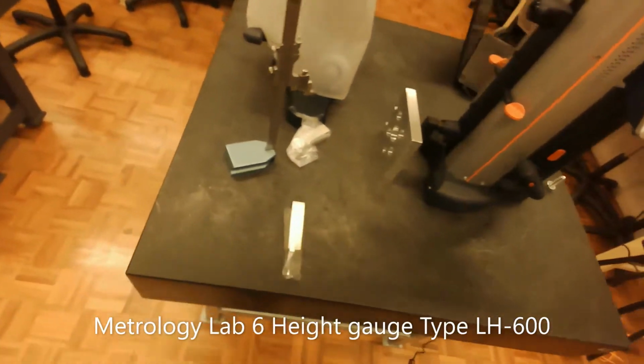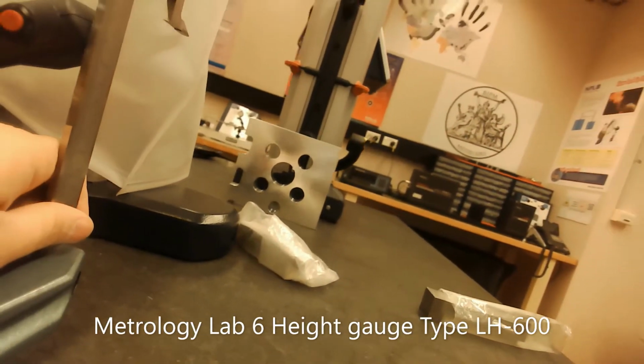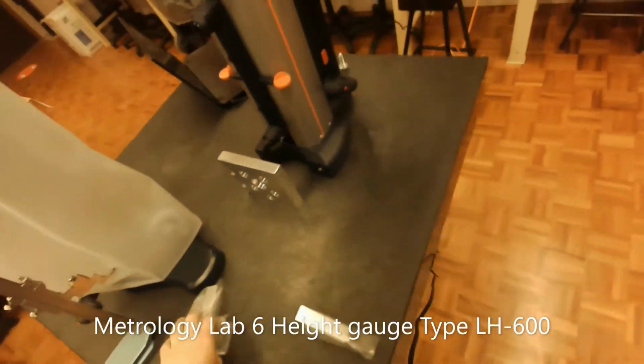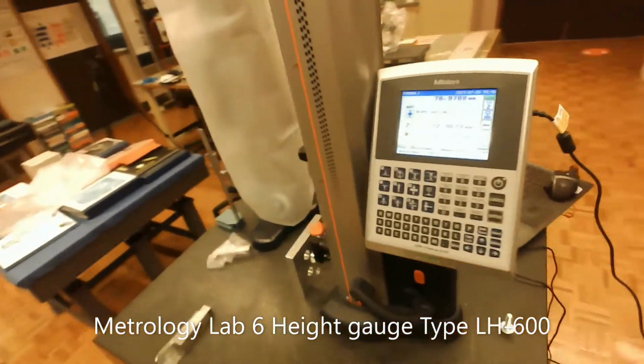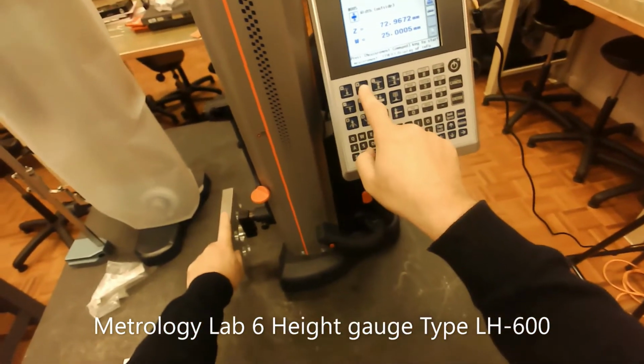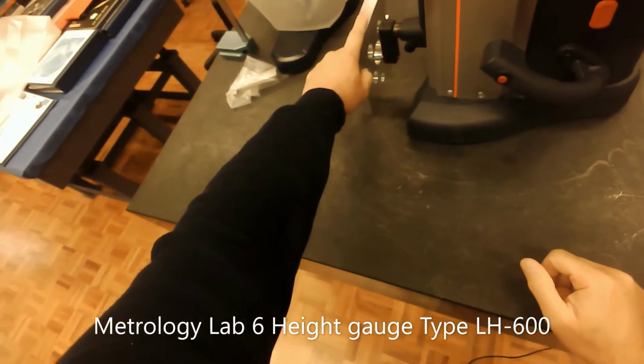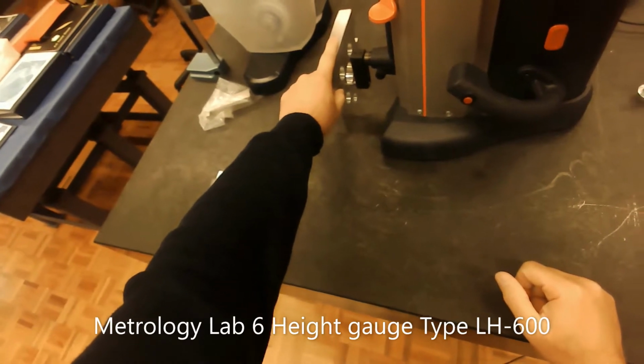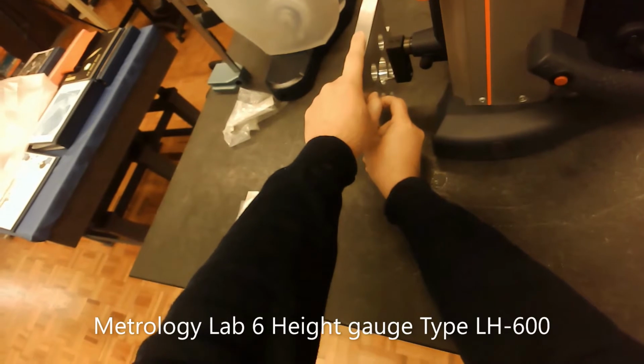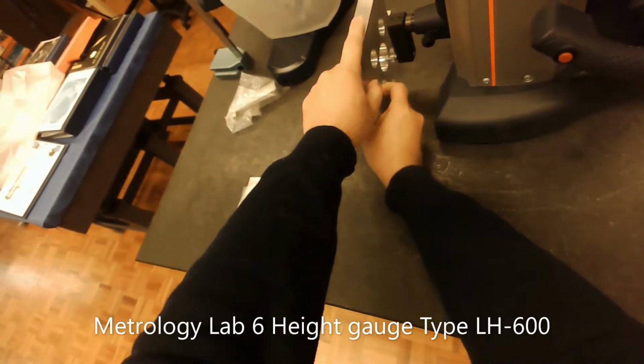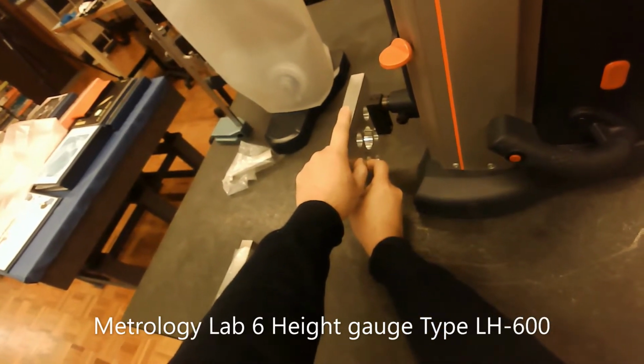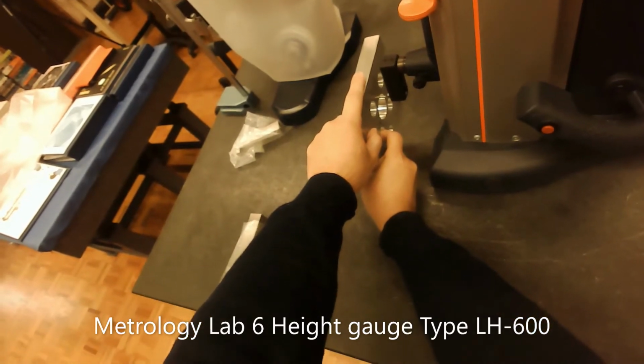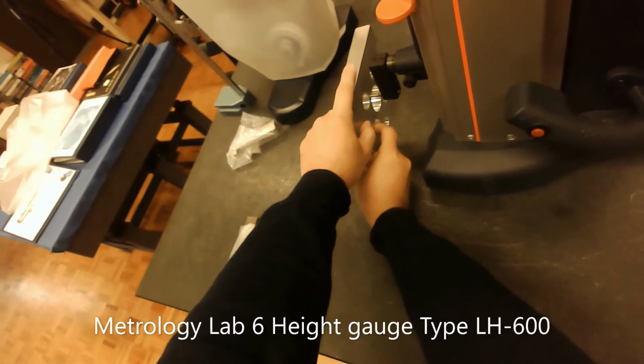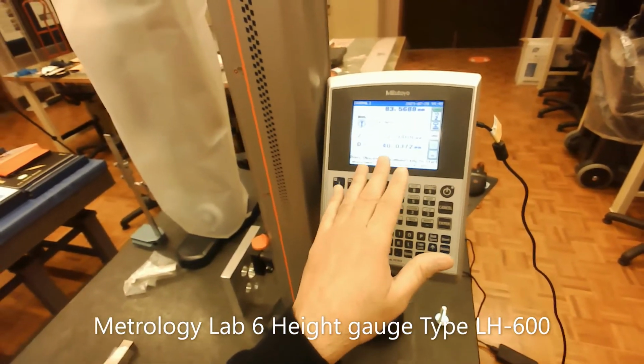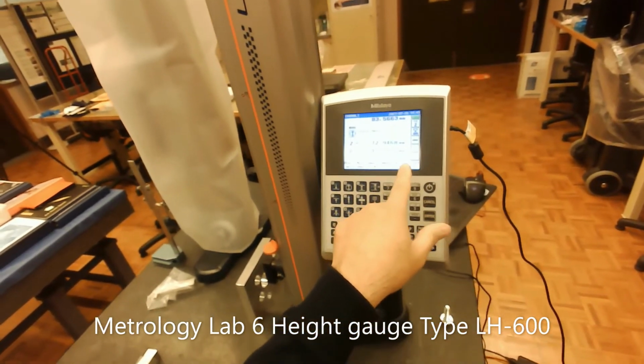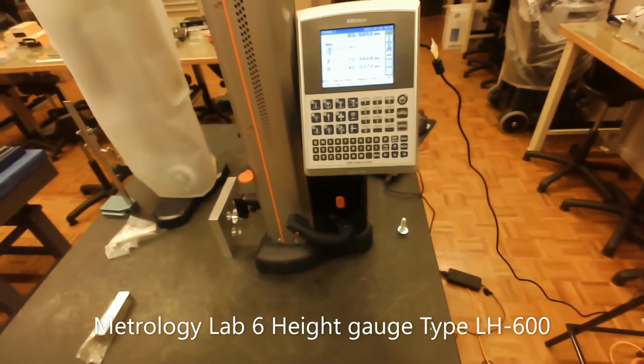If I take a look from the side, the probe is sitting in this position. When I explained it before, it was actually looking from this direction. Now, I'm going to press that, but I need to hold the part firmly first. Press that. Now the probe is coming down. Hear the beep. I start to pull the part toward myself slowly. Stop. Let it go up. Now start to push it the other way. Stop. Now, it's telling me that the diameter is 40.0372 millimeters.